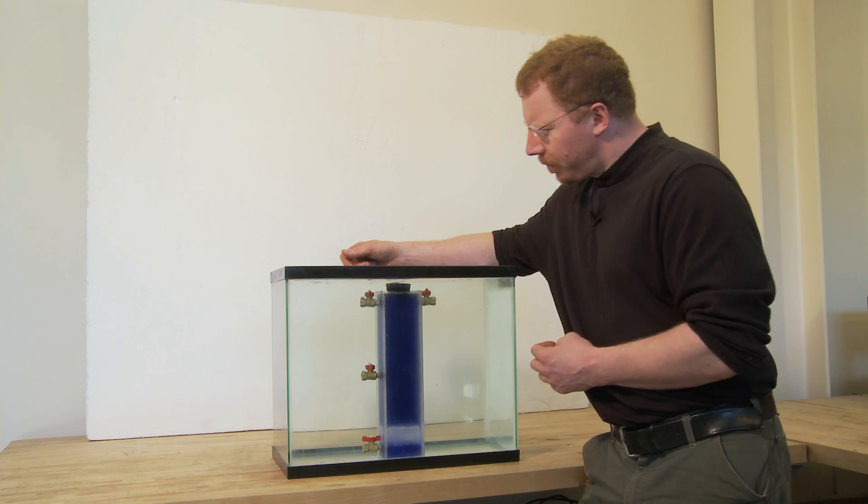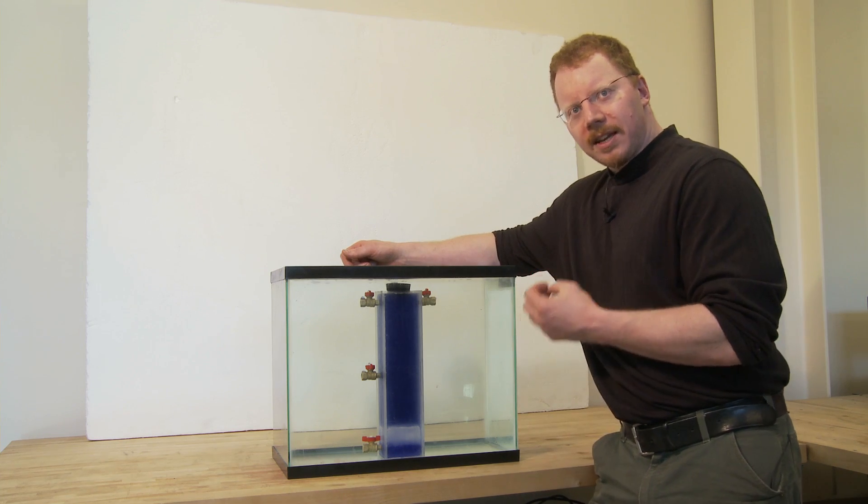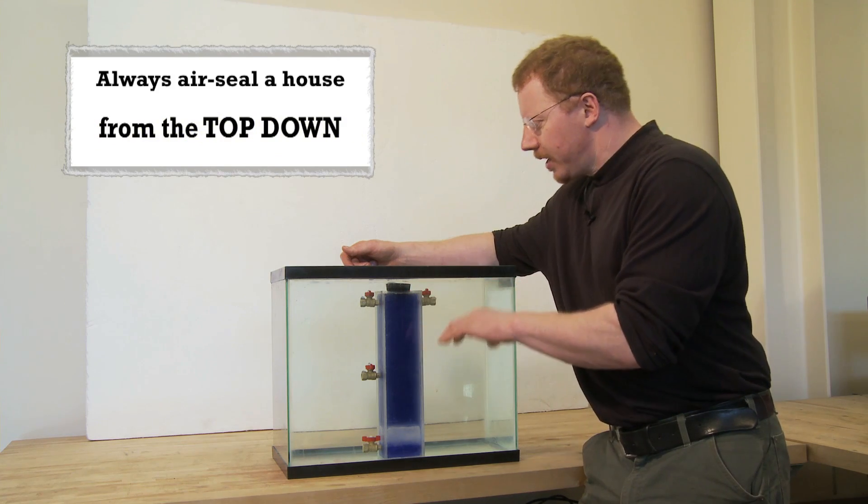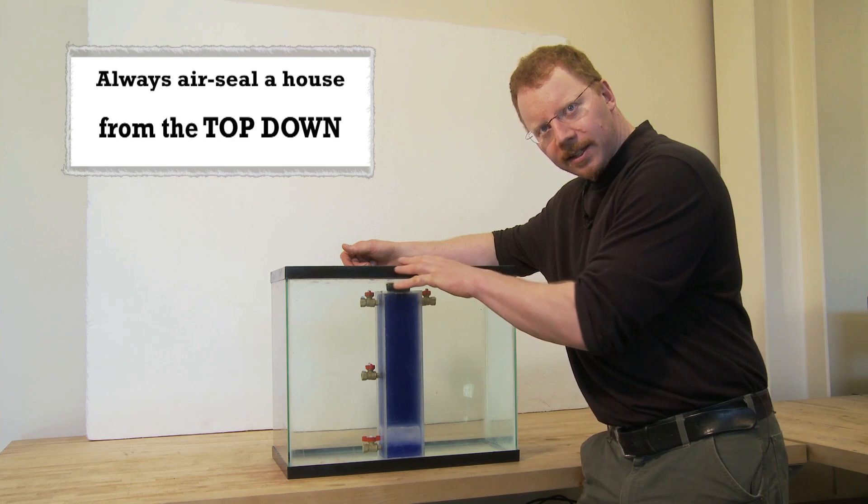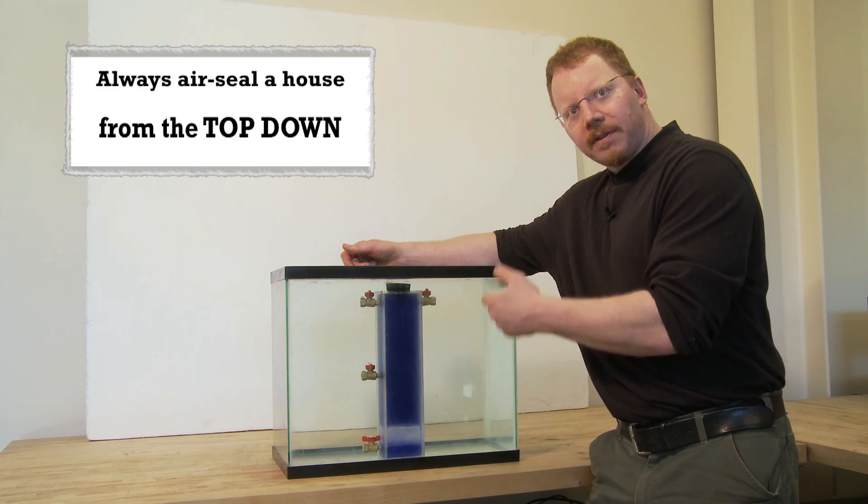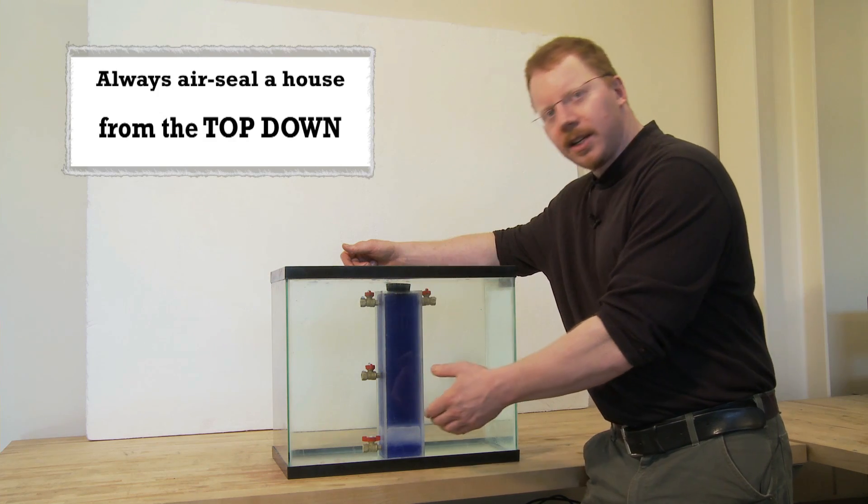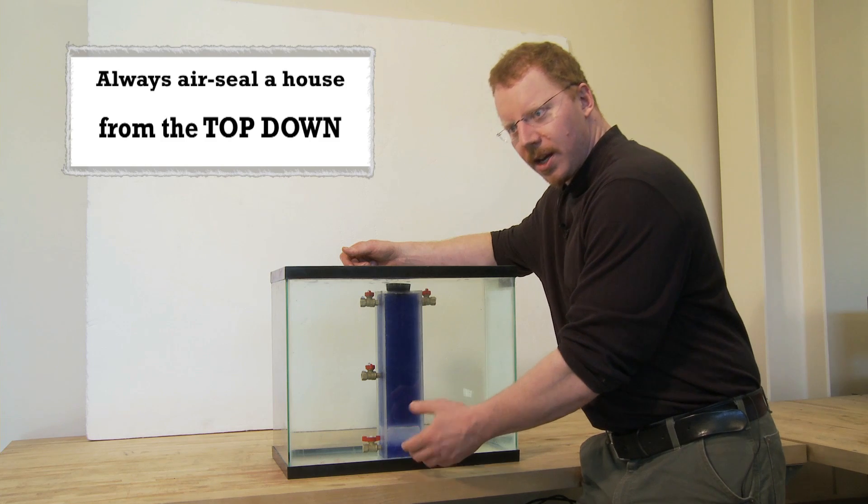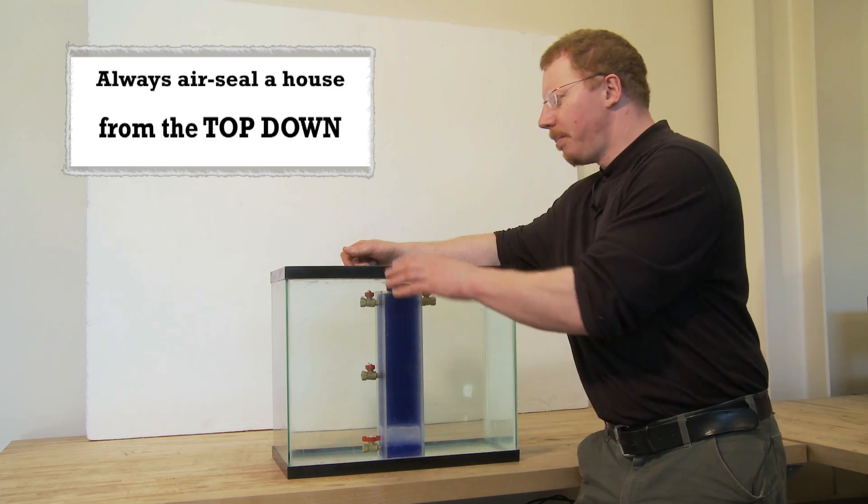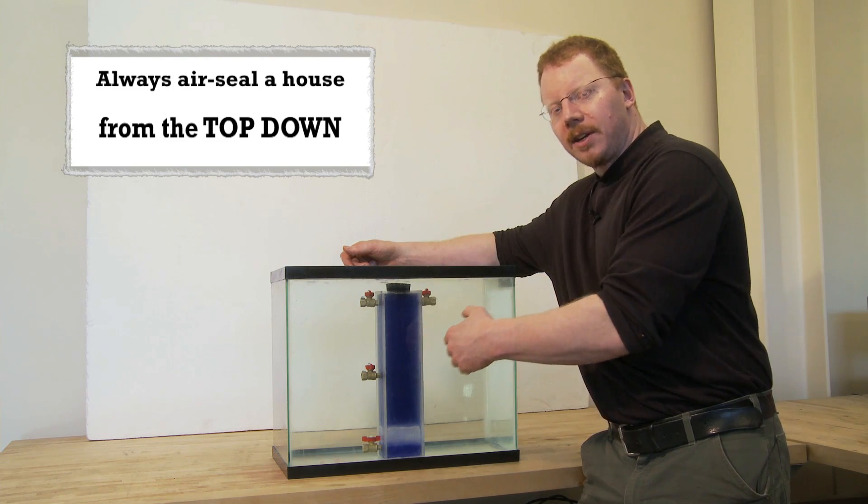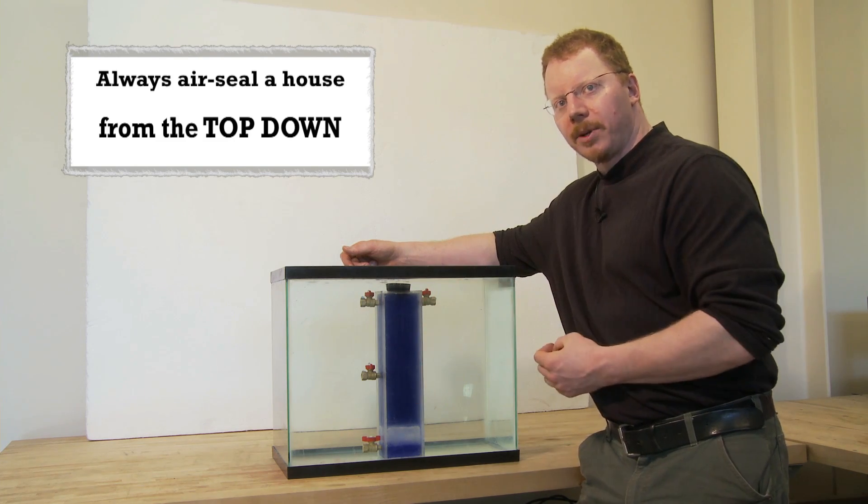This is a very important point. In order to most safely air seal a house, it's always better to air seal from the top down. If you close the holes off at the top, you will reduce that incentive to cause backdrafting of appliances and to have air leakage come in from the bottom. If you air seal from the bottom first, you're making a tighter house, but you're still leaking out of the top and your chances of backdrafting an appliance or causing other problems are much greater.